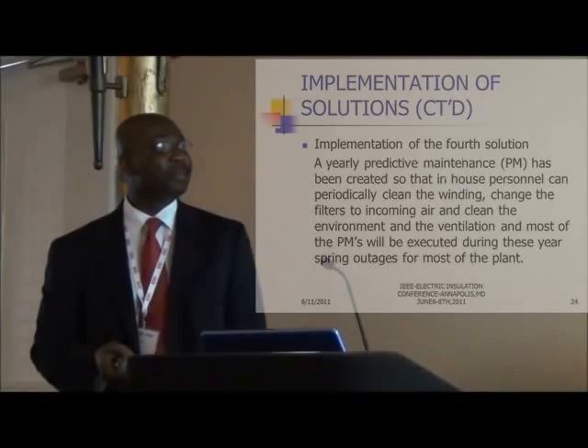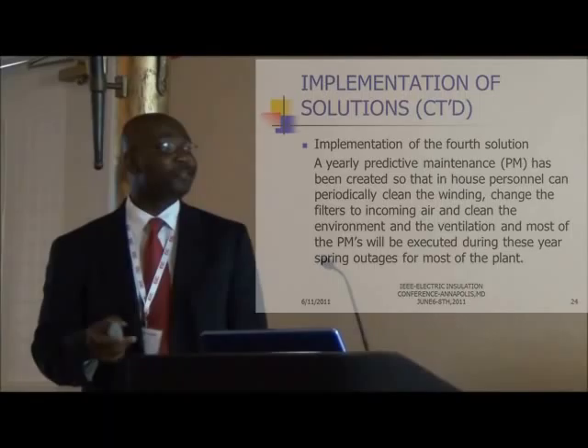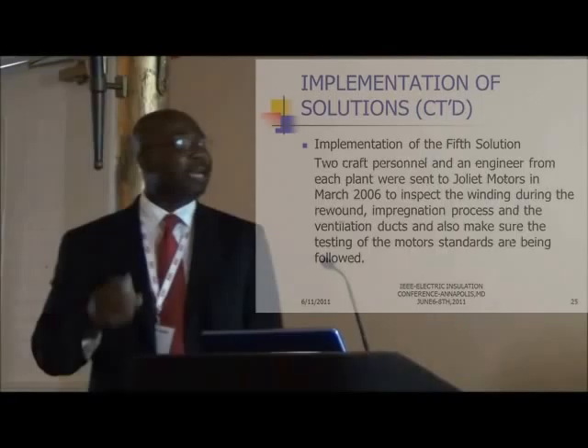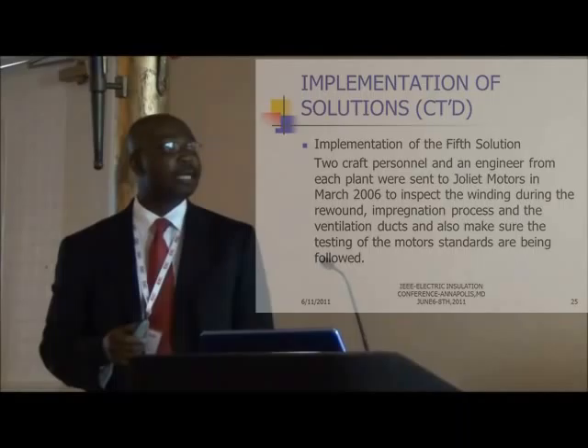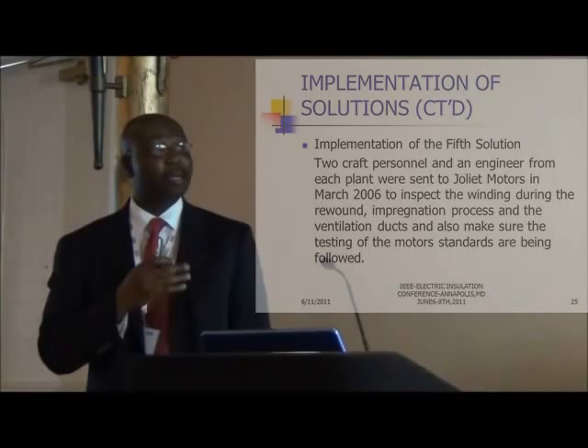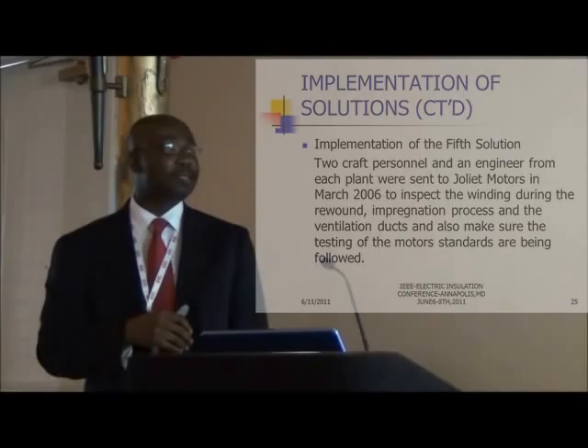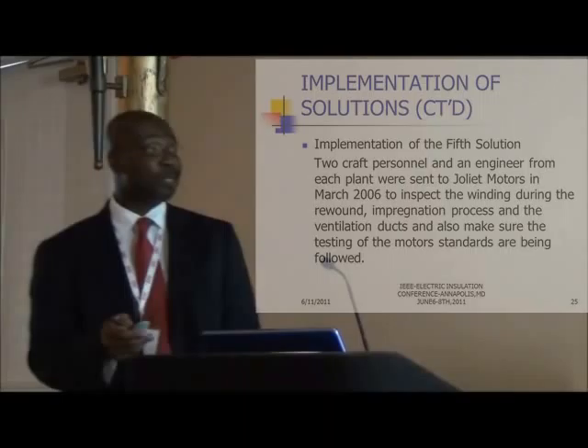A predictive PM was created for the craft to clean the windings, change the filters, and clean the environment and ventilation systems. We also implemented the proposal to have craft personnel and engineers physically go to the motor shop during repairs or rewinding to provide oversight over the winding process, the impregnation process, and to ensure all testing meets specification requirements.